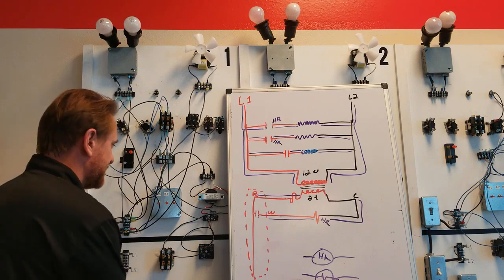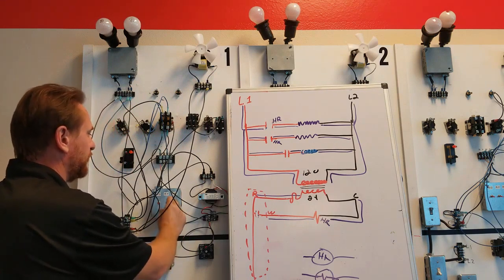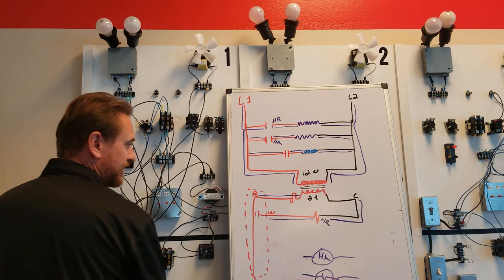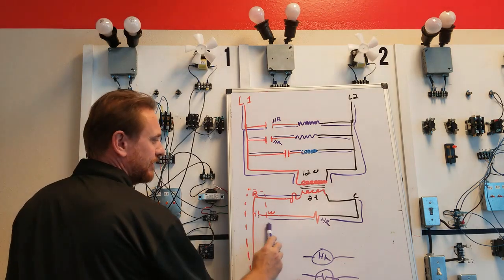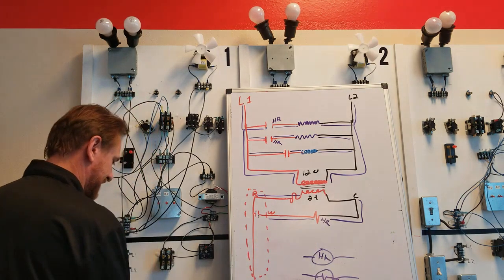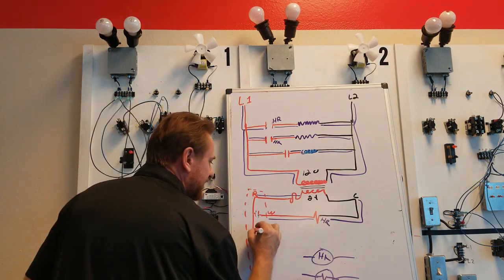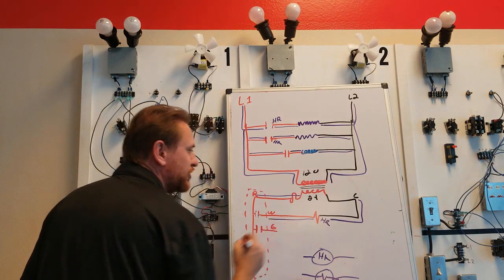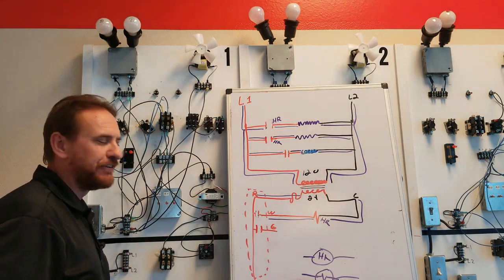Now that's done. My thermostat calls for fan, it connects R to G. Except down here we have nothing there, so we're going to have to add this. Our thermostat is going to have another switch with the letter G, which stands for indoor fan relay.